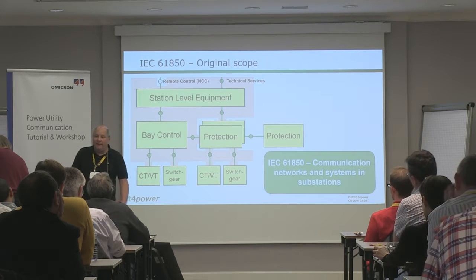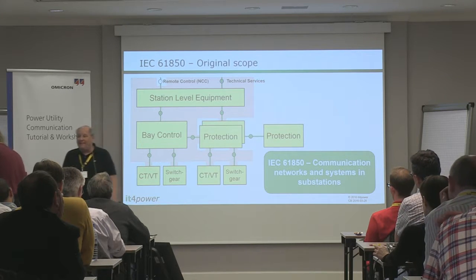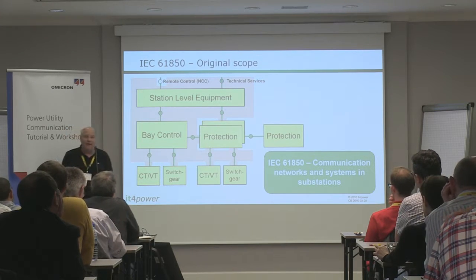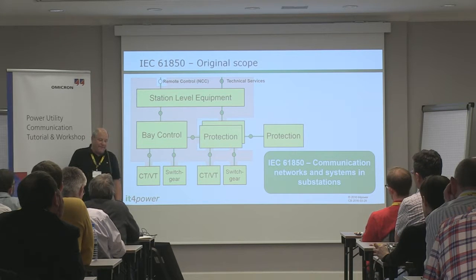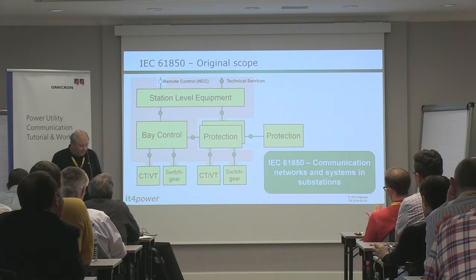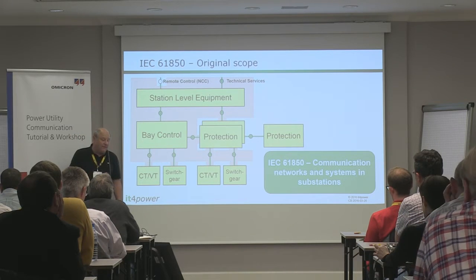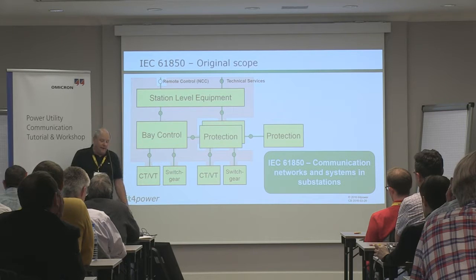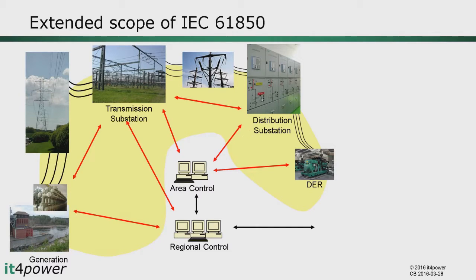Also relatively new with 61850 was the possibility to integrate the process bus — the direct communication down to the switchgear and the equipment out in the switchyard. That was really the original scope. The standard was at that time called 'Communication Networks and Systems in Substations.' Over the years, people identified the power behind the concept and there was increasing demand to extend 61850 to other domains, so today it covers more or less everything within the field of power system communication.